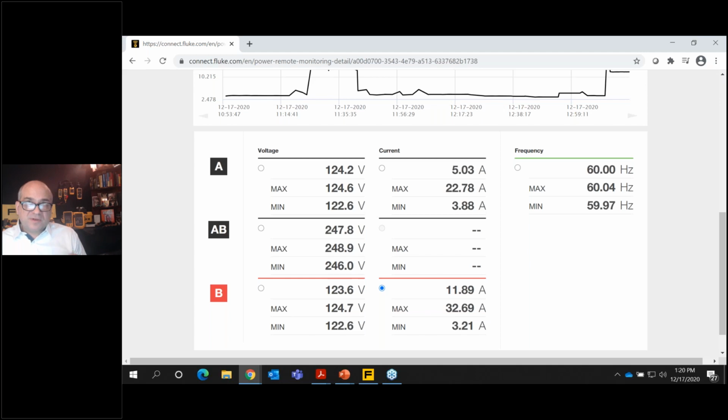And I use the example of an electrical wellness assessment on an annual basis, and there's probably some simpler words you could use to clean that up. It is much like a physical for us going to the doctor each year. We should do some kind of baselining electrically with our companies. And we should be talking about this, even though it's kind of like the test you don't ever want to talk about when you get a little bit older. You should have somebody put a power logger on your building and get a good idea if you're getting good power or not, as really inexpensive insurance, so you're not potentially blowing up stuff in an unplanned capacity, which is almost always more expensive than having a little bit of foresight.